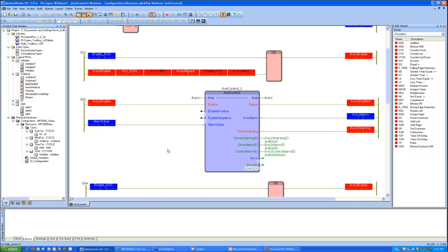So it's basically just taking three of the PLCopen function blocks, MC power, MC_ReadAxisError, and MC reset, combined into one. So at the very least, it's saving some code space in your project and also some debugging of additional ladder to incorporate all those features. And there you have it. One function block can handle those three things.